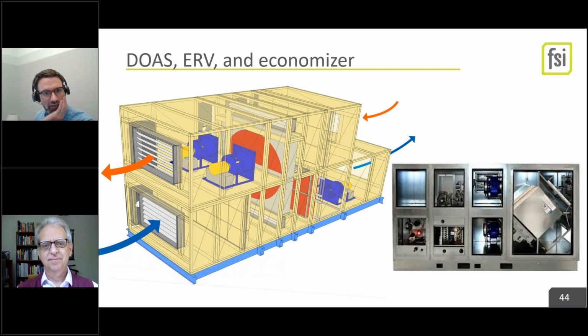And I'm getting lucky here because this one on the left has these teeny little dampers above and below that giant orange wheel. Those are economizer dampers, bypass dampers. So you can stop the wheel and bypass the core, and you can just sit there and push outside air in. There's like a 10-degree band, it depends on humidity as well, where it makes sense to do this, but it is an energy benefit over cooling that air. So the economizer is on outside air only instead of all of your airstream.